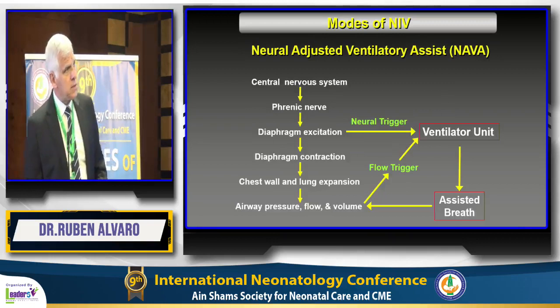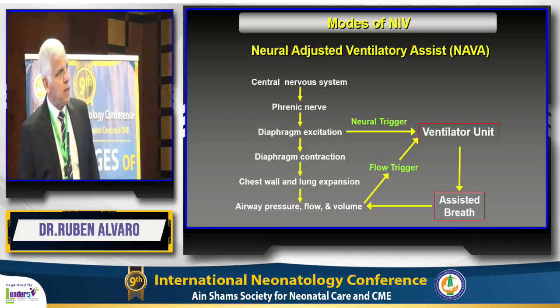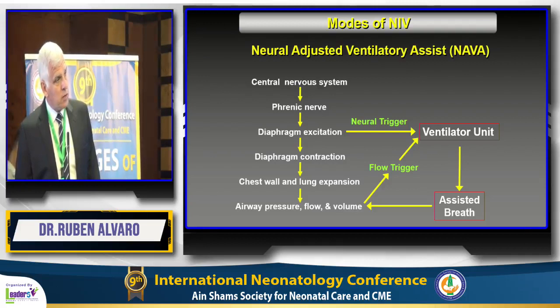Basically the way it works is that the baby will start breathing, okay? The impulse will go through the phrenic nerve, stimulate the diaphragm, and this fancy electrode will detect that excitation and send information to the ventilatory unit saying you need to start your breath now. But also, after the excitation, the diaphragm will contract, causing significant chest wall and lung expansion, and it will change airway pressure, flow, and volume. That also becomes a triggering mode for this machine to know how much pressure, how much assist, it needs to deliver for that breath.